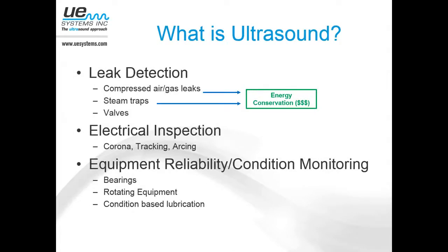Ultrasound really is used for 3 distinct application groups. Leak detection, whether we're talking about your compressed air system in your plant or compressed gases, we can use ultrasound to detect those types of leaks. We use it on steam traps, and we use it on valves for determining internal pass-through on a valve or leak-through on a steam trap. So from an energy standpoint, it remains one of the top technologies for those types of applications.